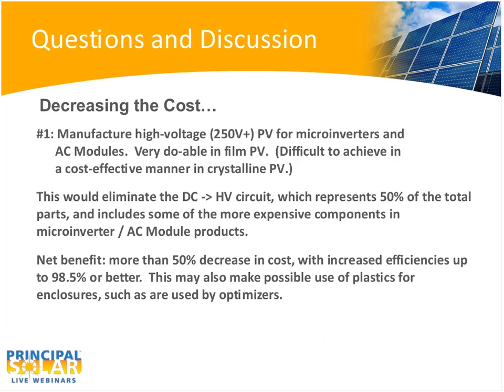Why? This completely eliminates the high voltage DC circuit inside the inverters. That's half the cost of the inverter right there, half the parts, and the more expensive parts at that: the inductors, transformers, higher voltage components. It literally reduces the size and cost of that inverter by more than half.